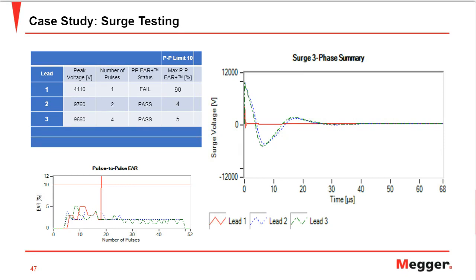And again, as the inductance changes, the ringing frequency changes, and the waveform of that particular lead moves to the left. So as red, or lead one, failed, you can see the waveform moving more to the left side, while the green and the blue are under the limits and almost in sync with each other. Even in this case, all the other tests which we do on the motor, the low resistance testing, the low voltage megohm testing, the PI (polarization index) and the DA, all passed.